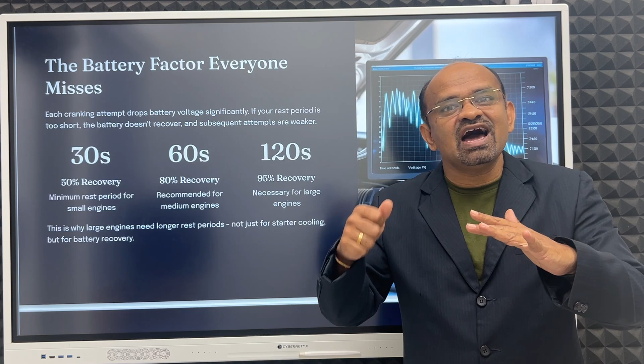30 seconds recovery gives 50% recovery, the minimum rest period for small engines. If it takes 30 seconds, 50% is the recovery period. 60 seconds gives 80% recovery, recommended for medium engines. Then 120 seconds gives 95% recovery, necessary for large engines. This is why large engines need a longer rest period, not just for starter cooling, but for battery recovery.